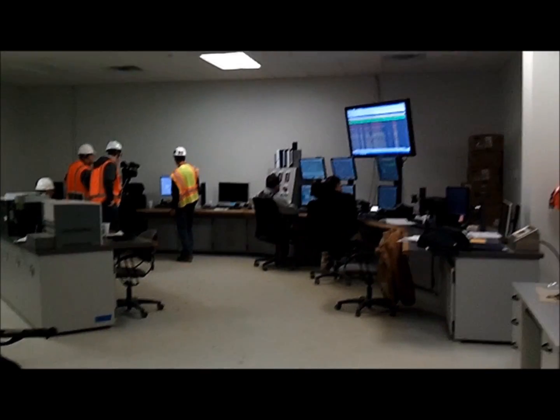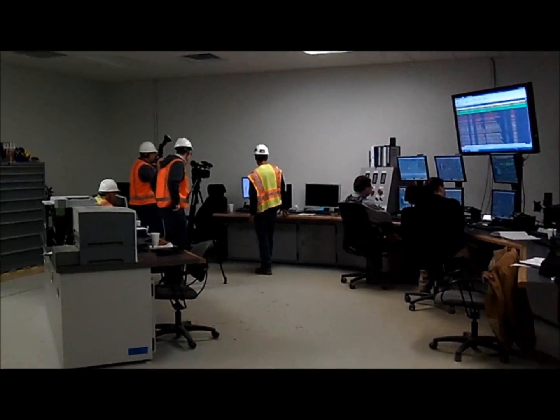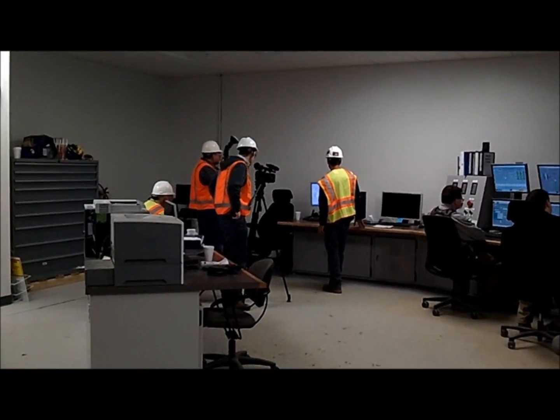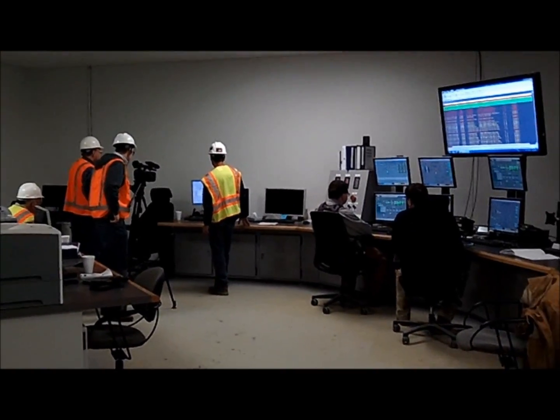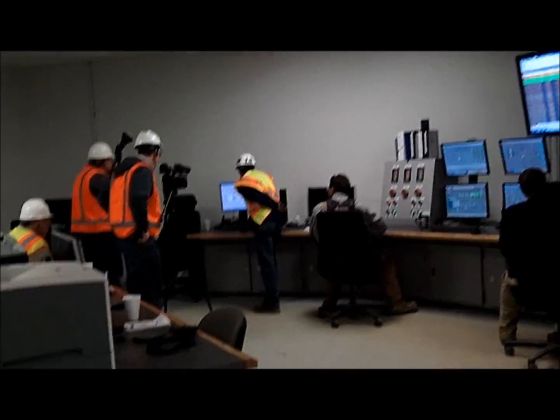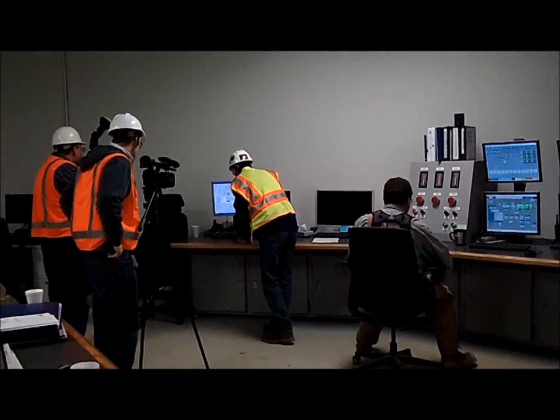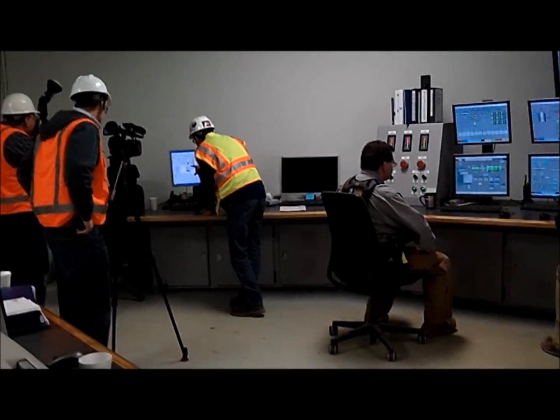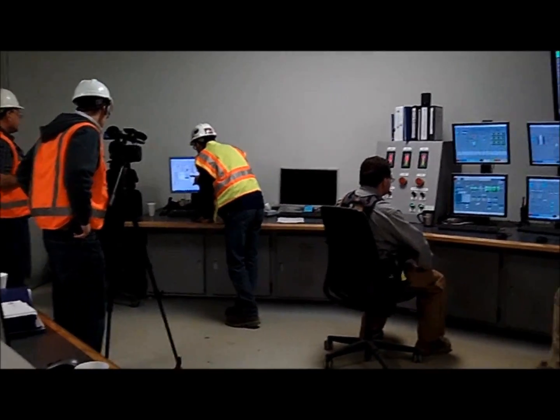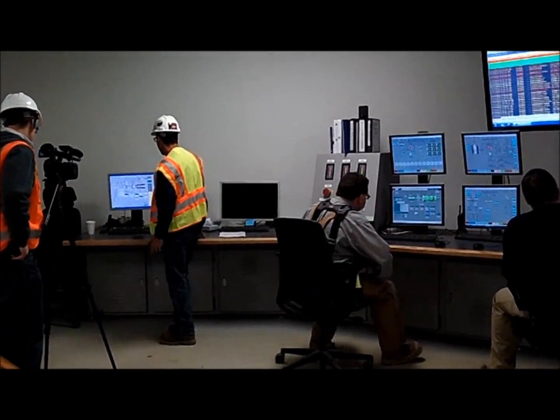We're in the control room at the Deer Creek Station and the turbine has been going through several tests this morning. They take it up to a certain number of RPMs and then trip it just to see how all the systems are working. Right now they're doing the false first fire, which is basically everything they would do during a first fire except there's no spark plug, so there's no fire. From there, the next step is the actual first fire.